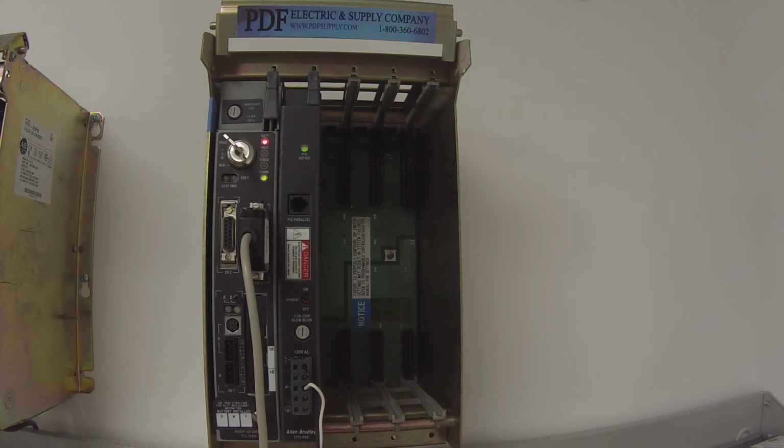Now this is the part where, as it's going through the download, it's going to check to make sure that everything is correct, as I was describing before. So it has chosen to correct me on the revision in the series. I'm going to go ahead and say OK, because it can see what it really is, and I may have checked it before I put it in the slot. And it's also asking me that there is a difference in the IP address. Am I sure that I want to change it in order to test it? In my particular case, yes. If you already have an IP address that it's working at, you can go ahead and keep that. Alright, so I'm going to say OK. Now the downloading processor image screen is going to pop open as it finishes the download.